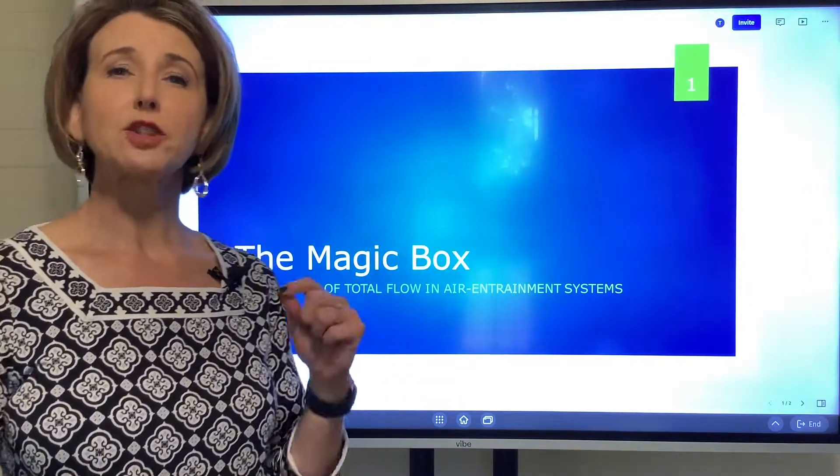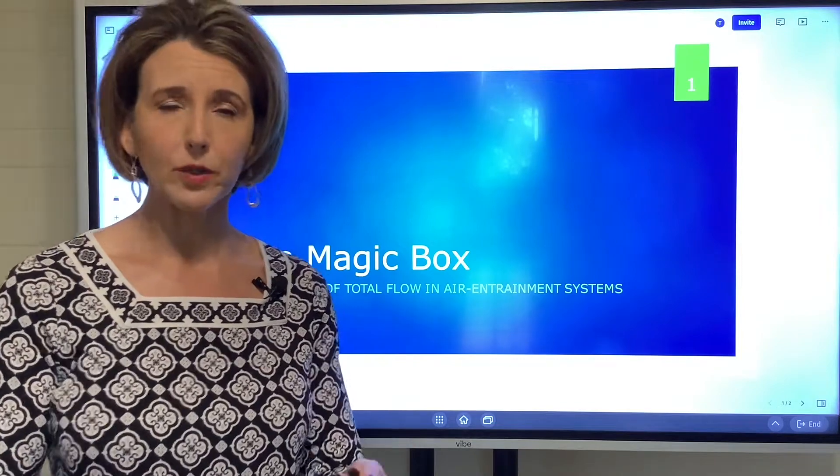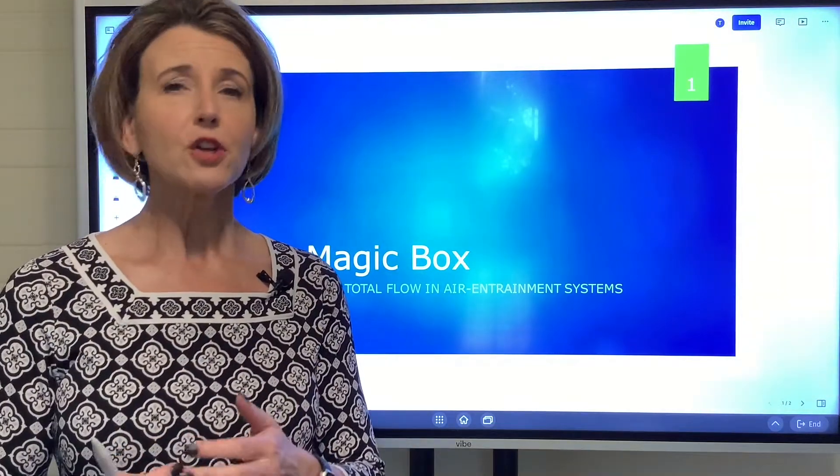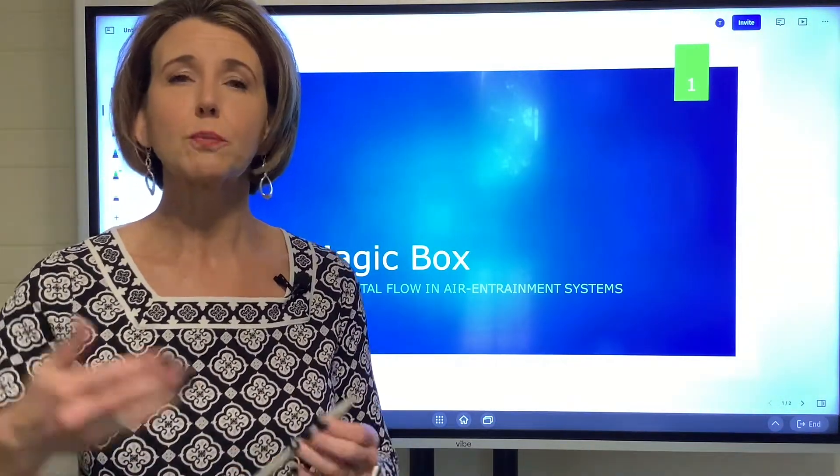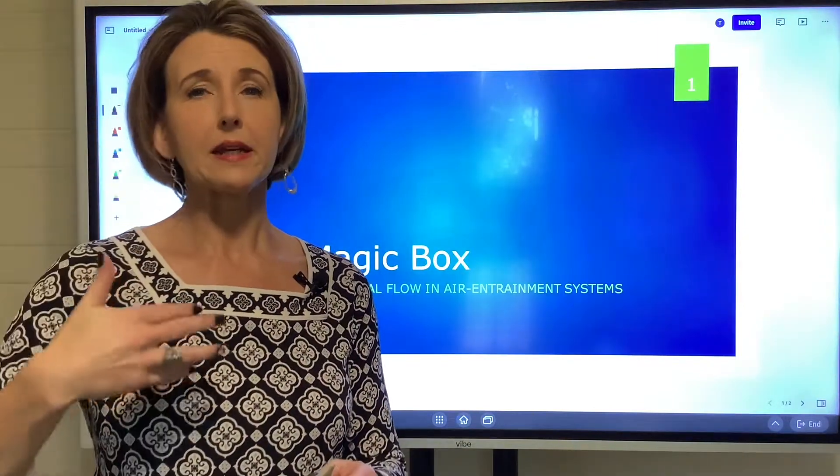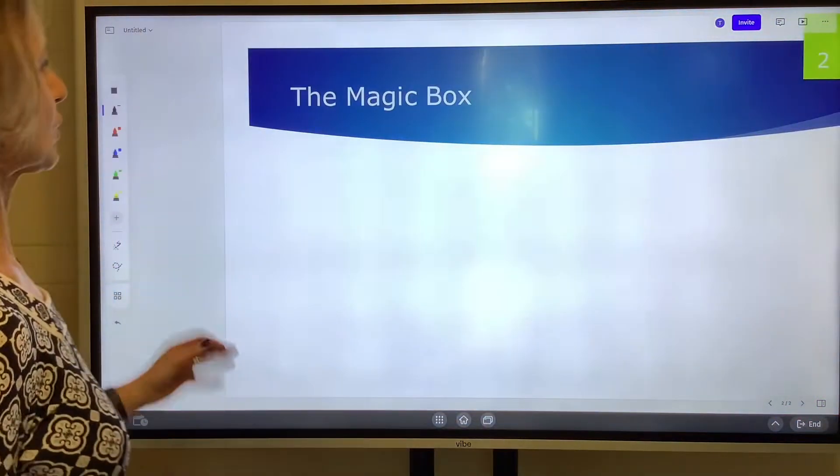The purpose of the magic box is to figure out the total flow of the device. So basically when you put that on the patient, you're delivering a specific FiO2, but it comes up into their airway at a certain speed—the total flow from whatever device we're using.